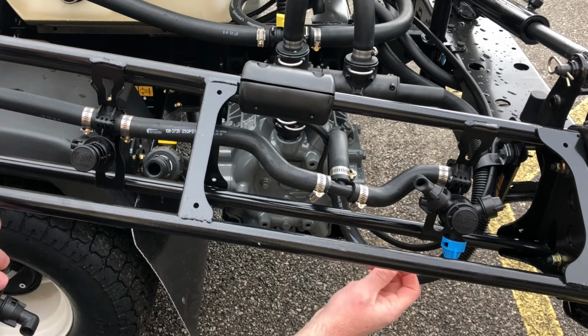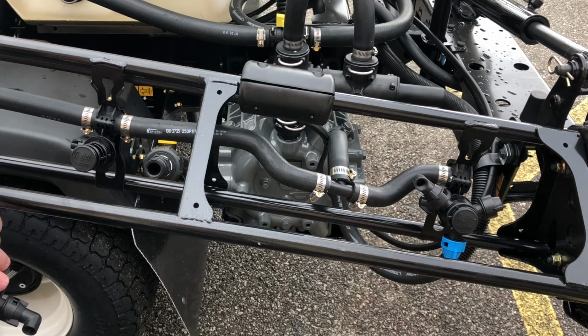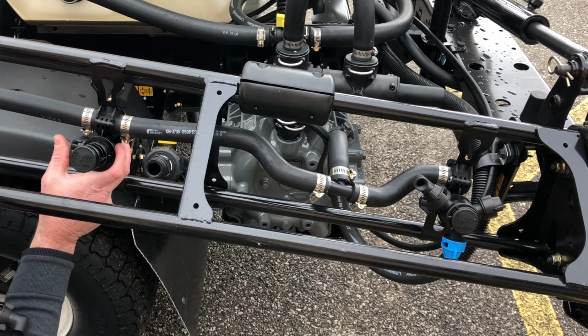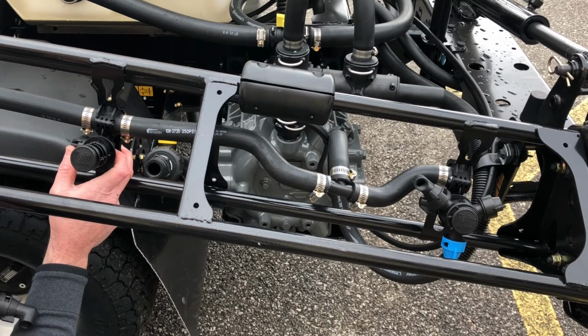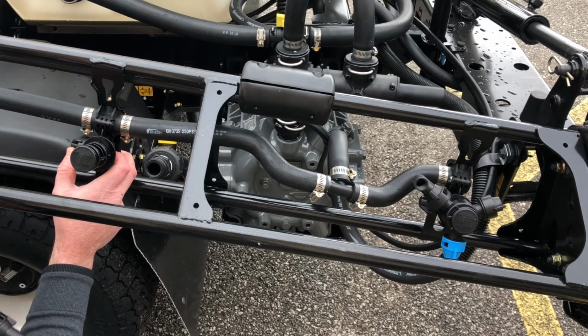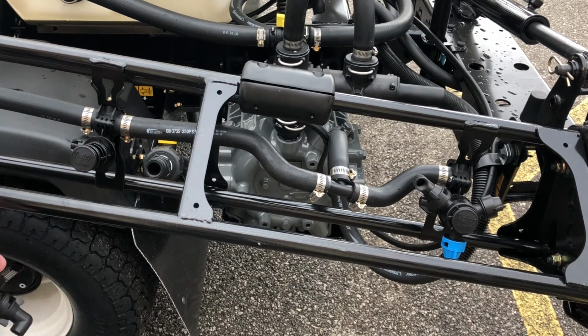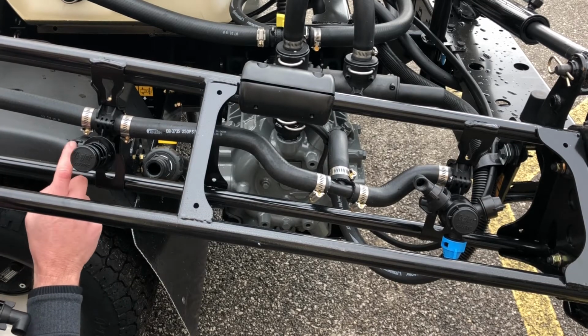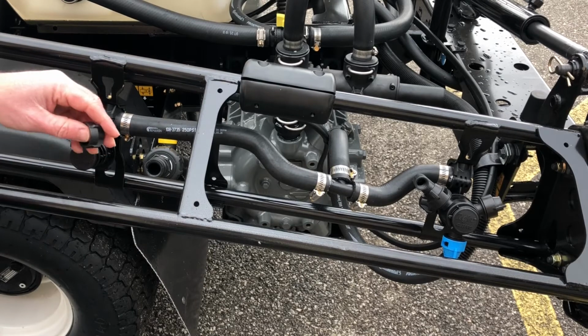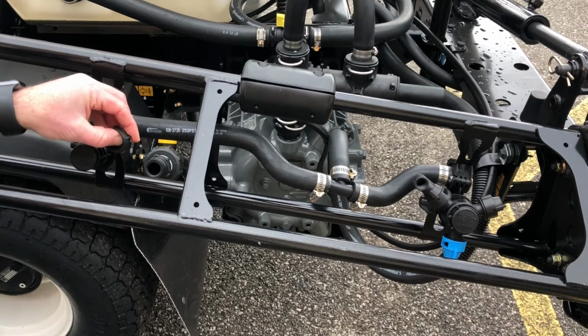So if you turn your nozzles off and get some drip, what's happening is the check valve on the back side of the turret itself needs attention. You should change that when you change your nozzles. So if you change your nozzles every year, spend the extra $5 or $6 per turret assembly and change these as well. It's just a little spring-loaded check valve.